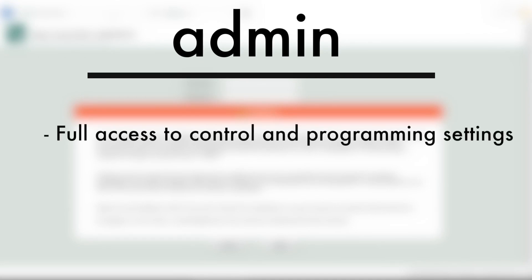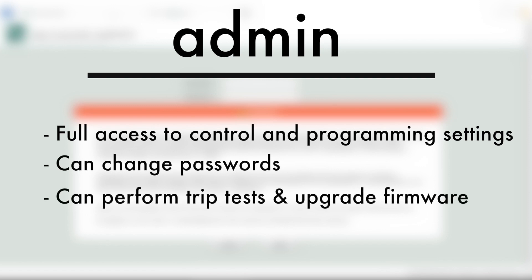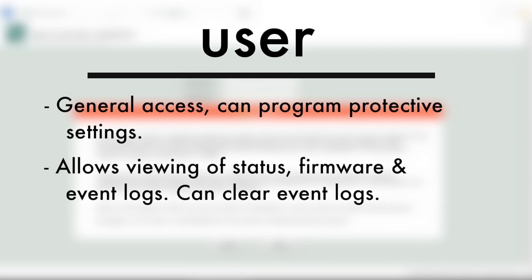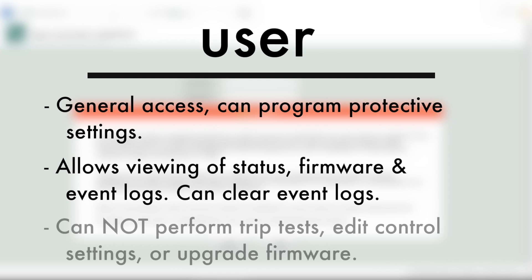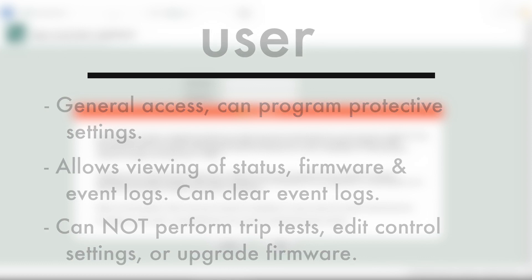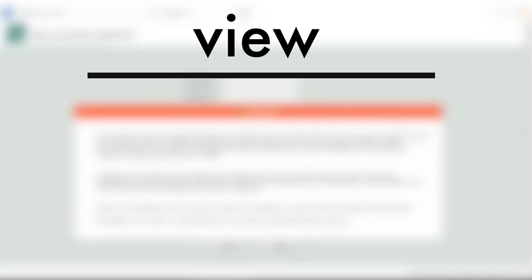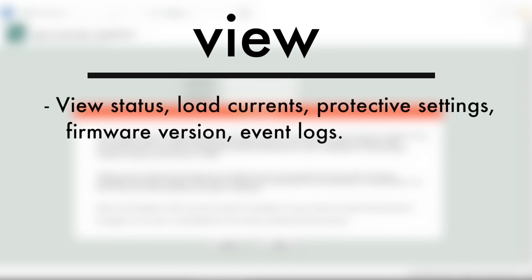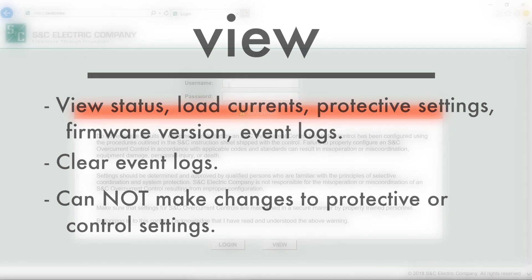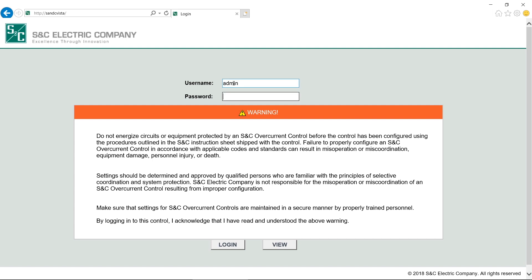Let's look at the differences between each login. The Admin Login allows the user to have full access to the overcurrent control, allowing programming of the protective settings and the control settings, as well as permission to change both the user and admin passwords. The Admin can perform trip tests and upgrade the control's firmware. The User Login allows the user to program the protective settings and view the status of the control, firmware revision, and event logs. The User Login can also be used to clear event logs. No changes to the protective settings or control settings can be made. For our purposes, we will log in as admin, as if it's the first time we're using the software.